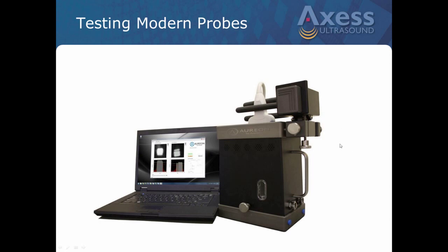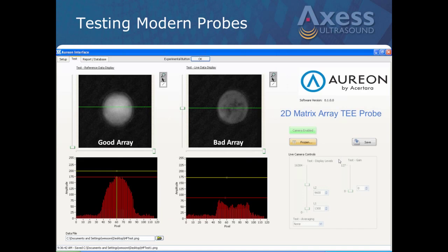Leakage testing, obviously, and again, I hope you're doing that, especially on transesophageal probes. Live testing and the proverbial tissue phantom is also a good way to test probes for a baseline. One of the new devices out by Axess is called the Aureon. This device is rather unique, I think, now in the industry. Unlike the FirstCall, you don't need a lot of adapters for each probe. You basically can test any type of probe on this device just using the machine.